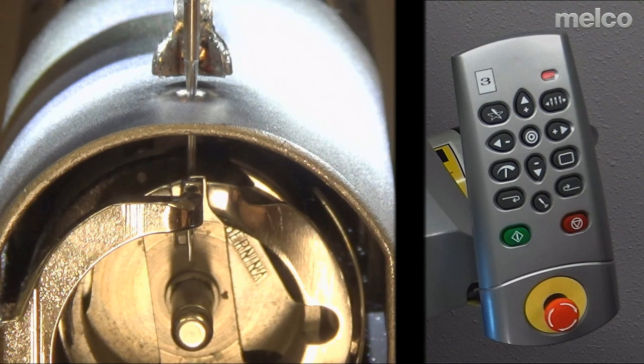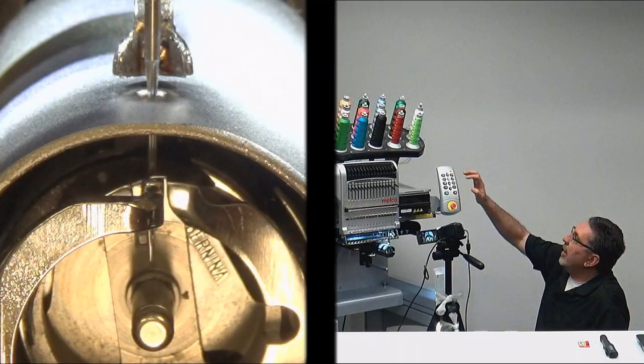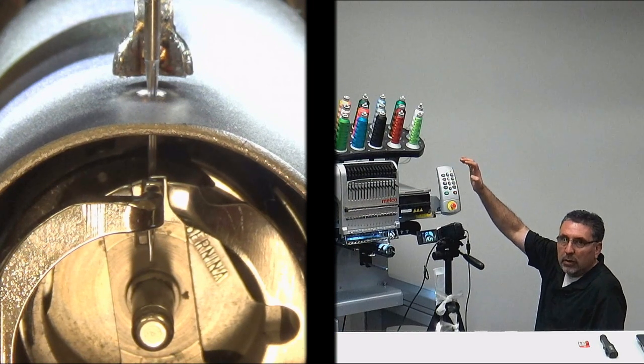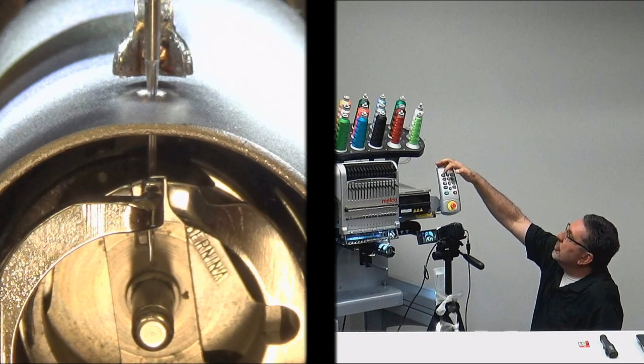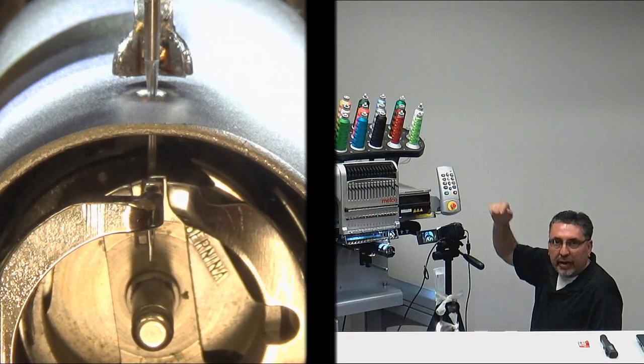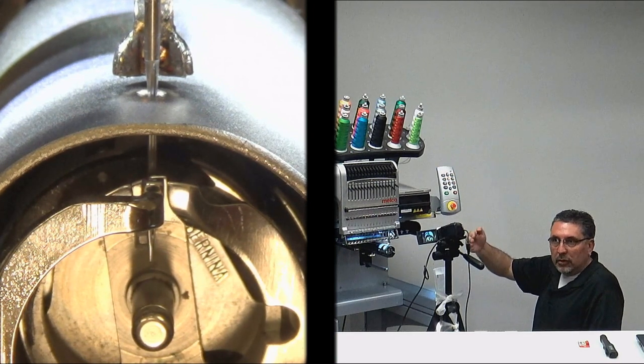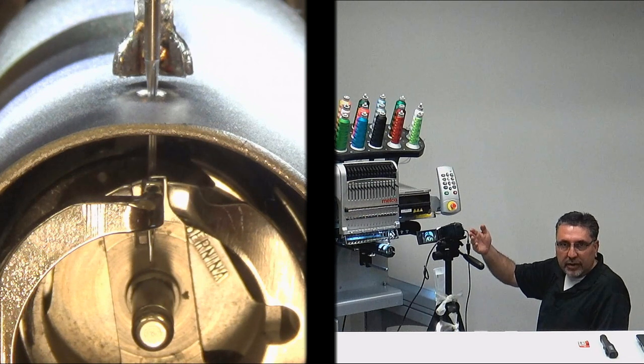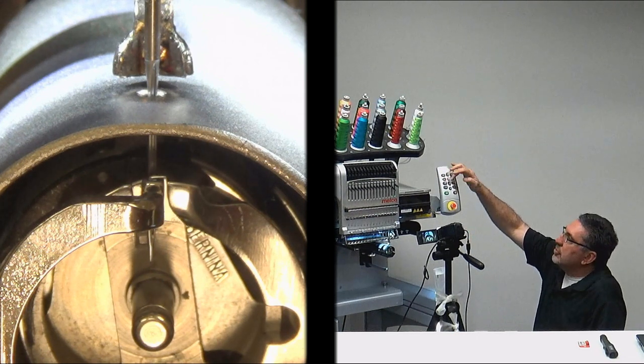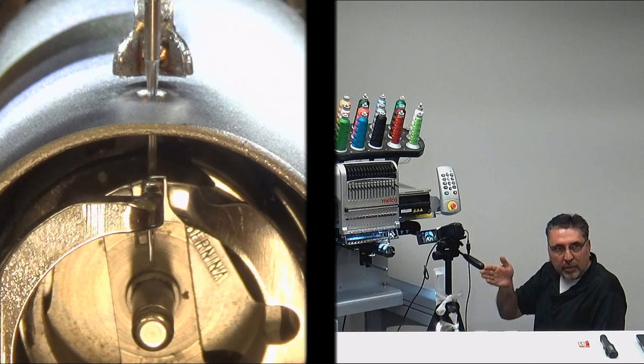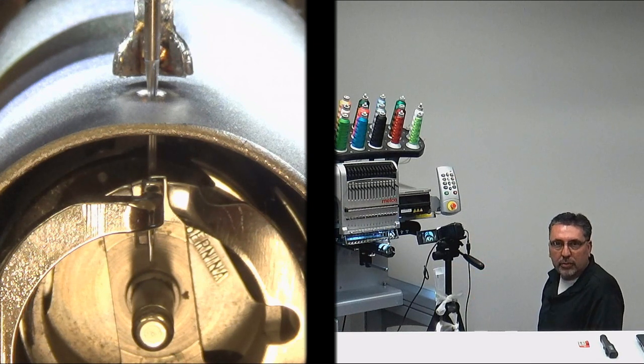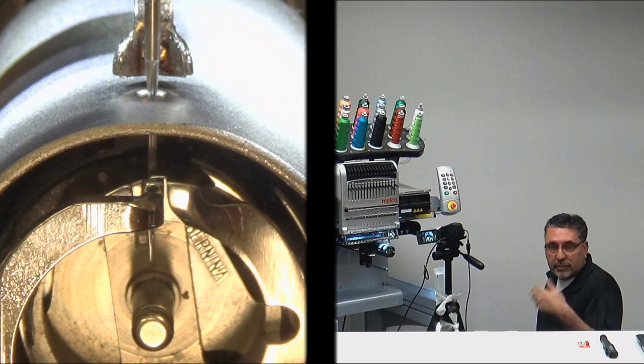If it was incorrect, I would do an adjustment up arrow. And then I would use my trace button and my left or right arrow, and I would move the needle case a little bit each direction I needed to go. I would do an adjustment down and check my centering left and right to the needle plate hole. So as you can see, needle number 2 is pretty well centered right up.